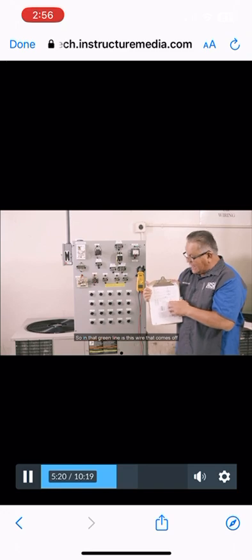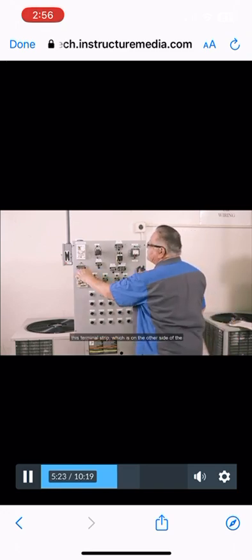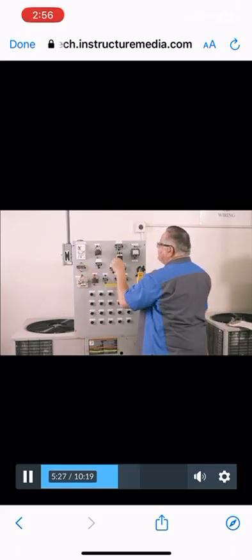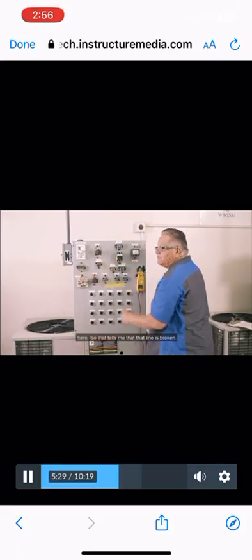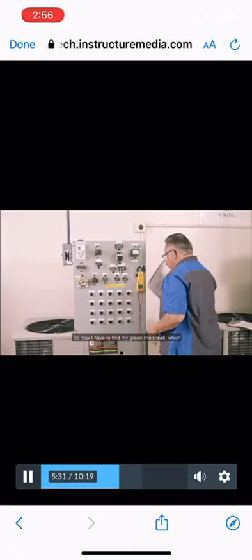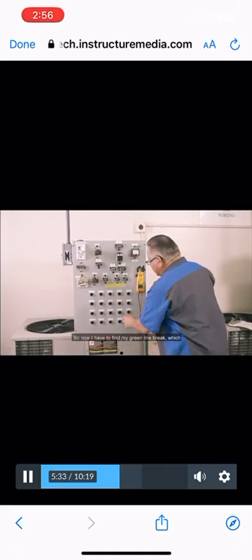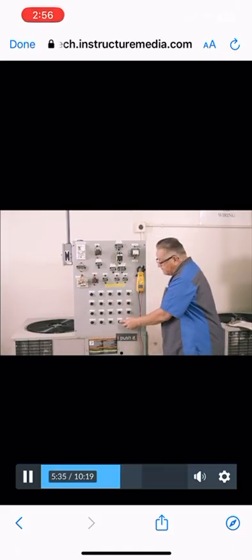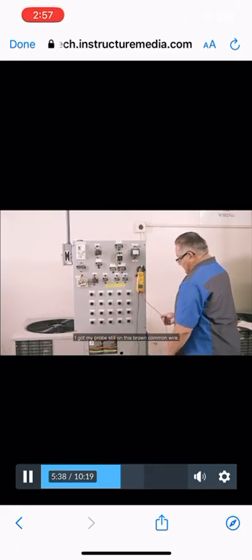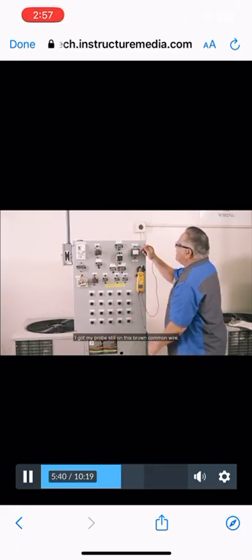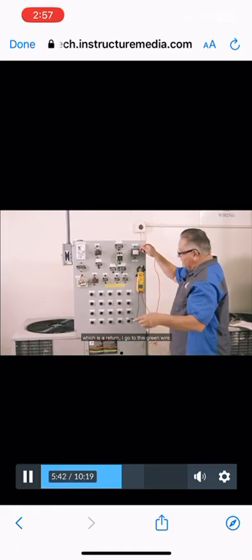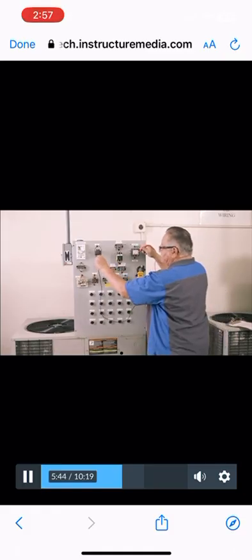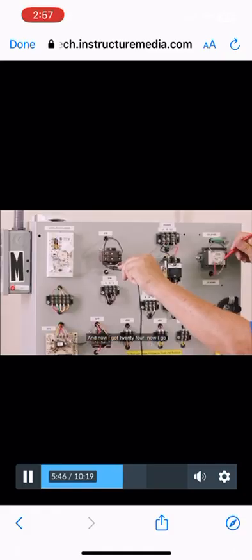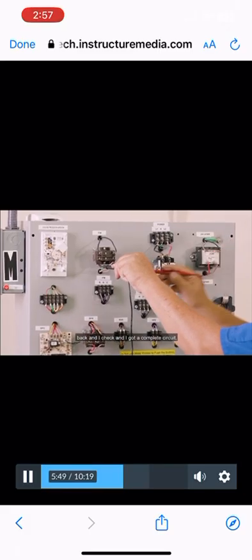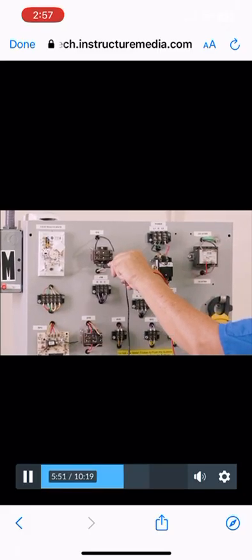So that green line is this wire that comes off this terminal strip, which is on the other side of the hole again, and it goes from here to here. So that tells me that that line is broken. So now I got to find my green line break, which is this button here. I push it. I got my probe still on this brown common wire, which is a return. I go to this green wire, and now I got 24. Now I go back and I check, and I got a complete circuit.